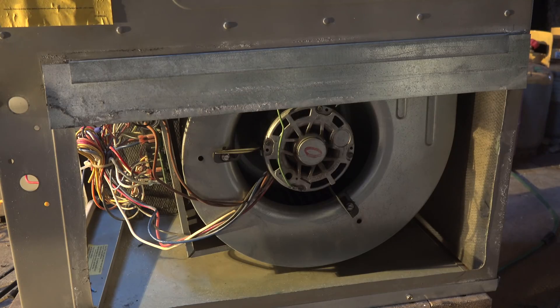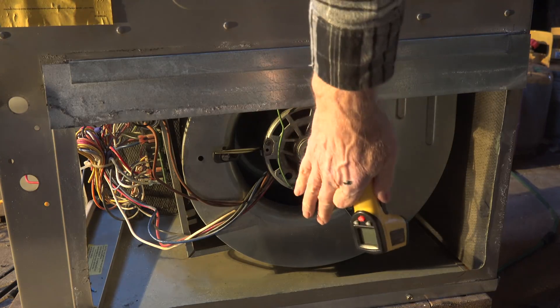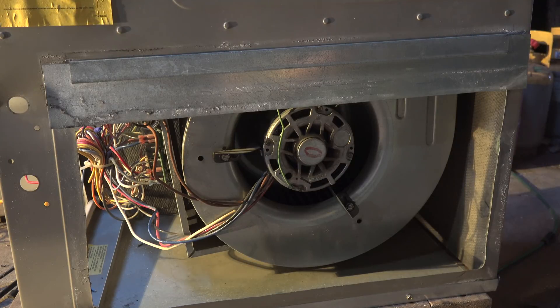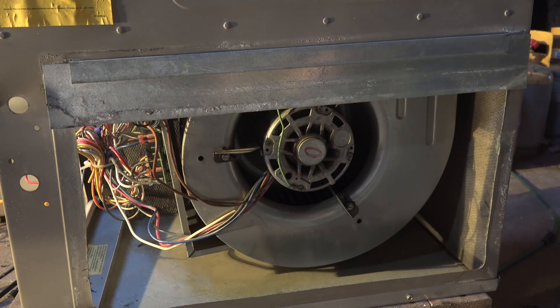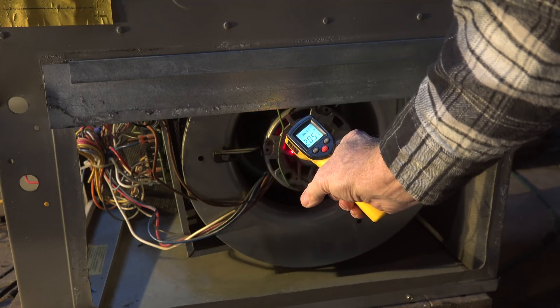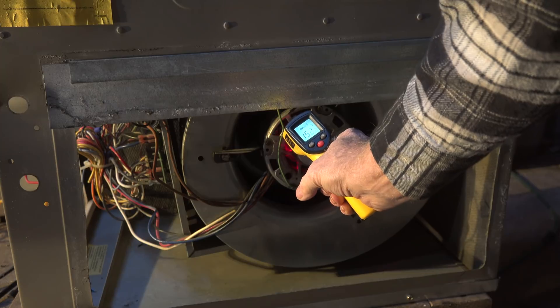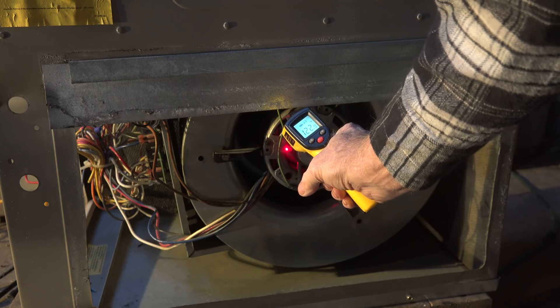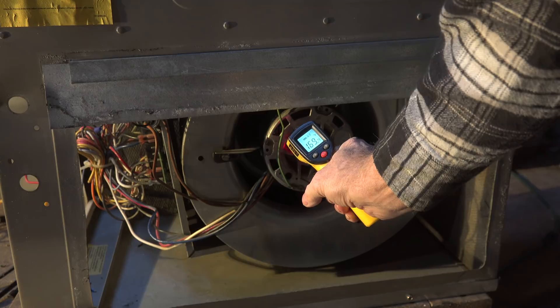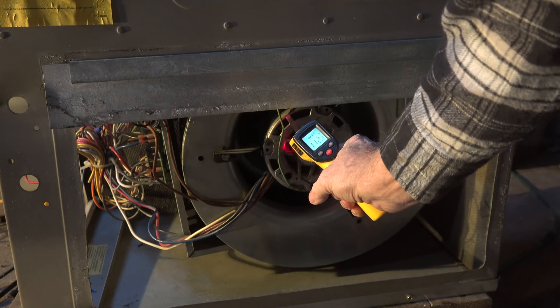Because I'm working with a test mule here that just came out of the junkyard, I've got all sorts of options — there's no ductwork hooked up, this is where the return air should be. What I want to find out is if there's power to the fan. This is in Fahrenheit and showing 208 on the outside, 155 inside — there's a lot of different numbers here, but the one common denominator is it's hot.